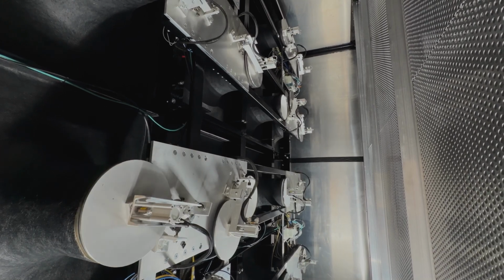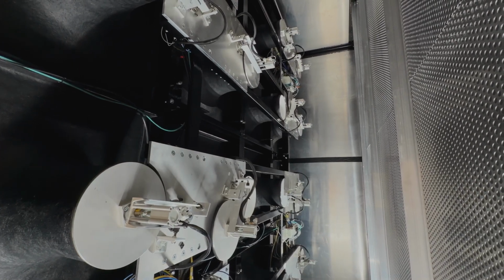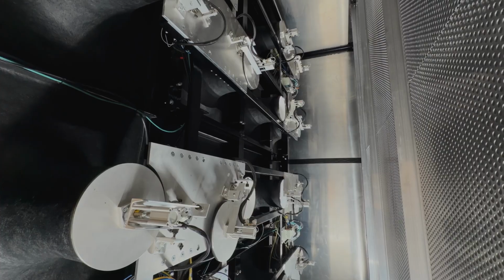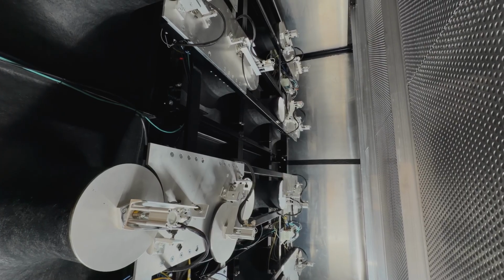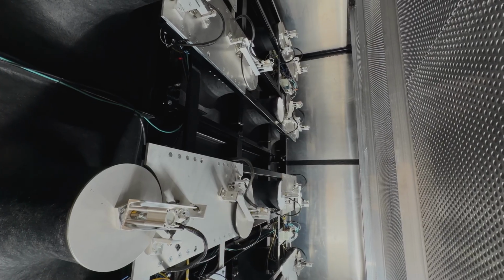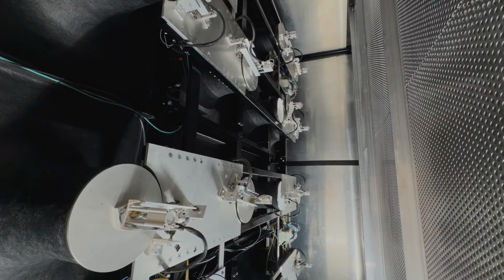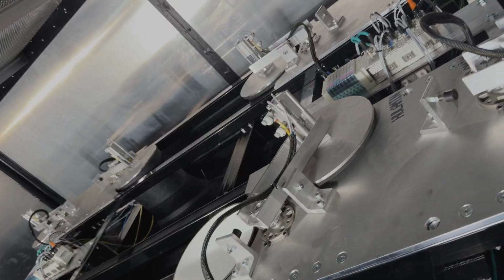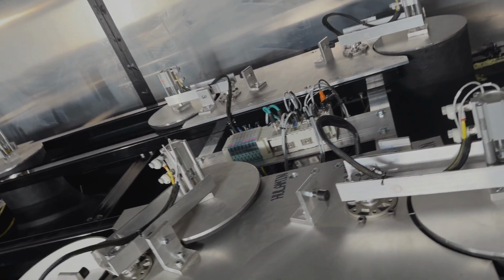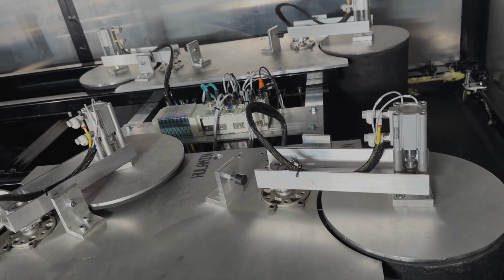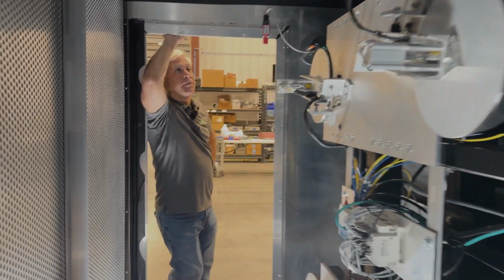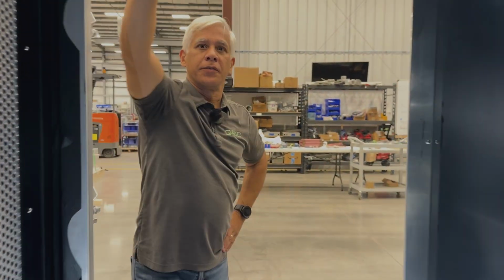For testing a particular fan array, we're looking at somewhere in the neighborhood of 100 test points. And to go in here and change nozzles one at a time manually means shutting down the tunnel, cutting power to safely walk in here, reconfiguring it, coming back out, and restarting the test. In order to collect the data quickly, efficiently, we have designed this tunnel to be fully automated.